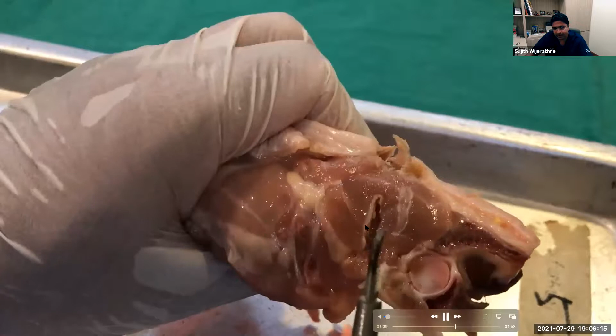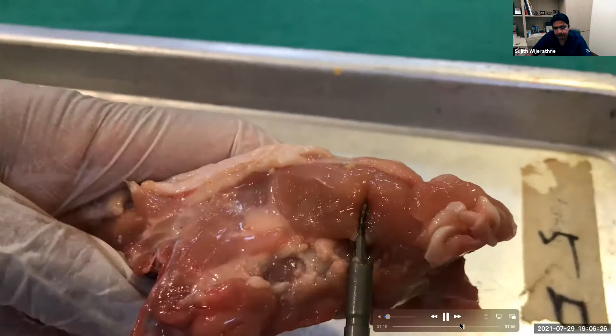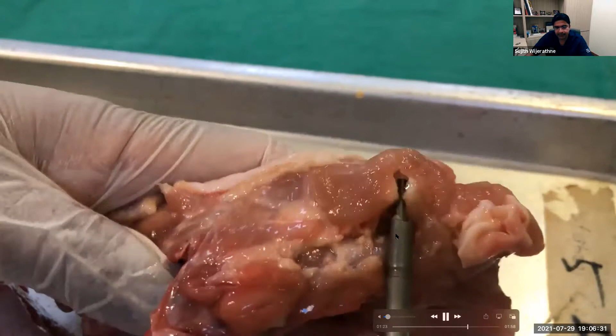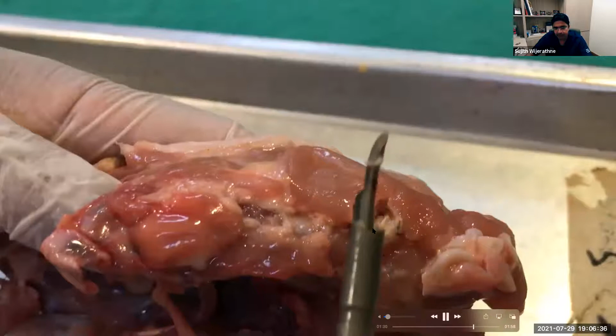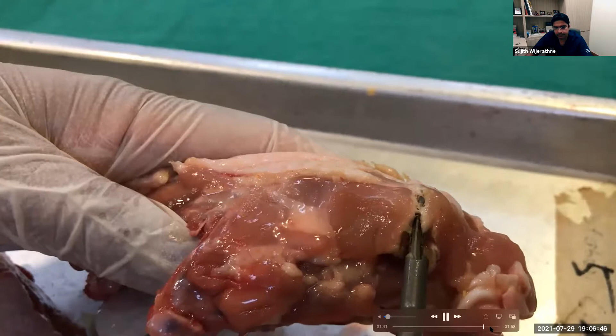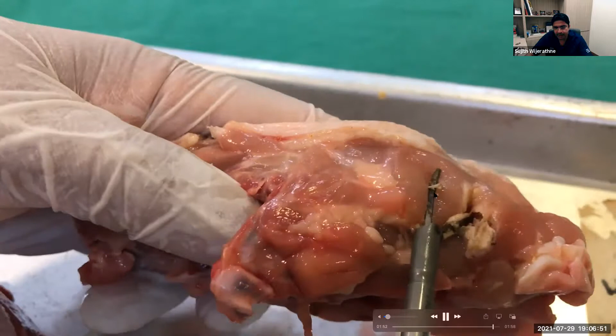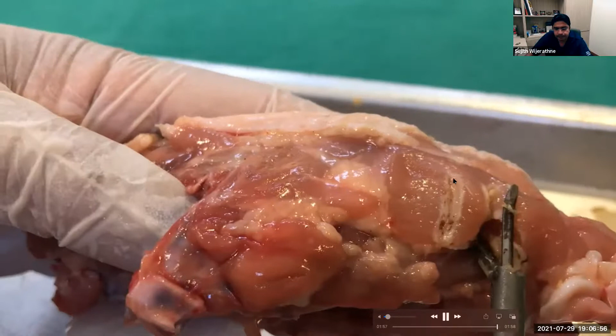If we see this in an infrared camera, you should be able to see how far it spreads. This is where I'm using ultrasonic energy, cutting and sealing at the same time. You can see the amount of thermal damage that has happened. This is without activation. You can see the amount of residual heat that it contains to burn the tissue.